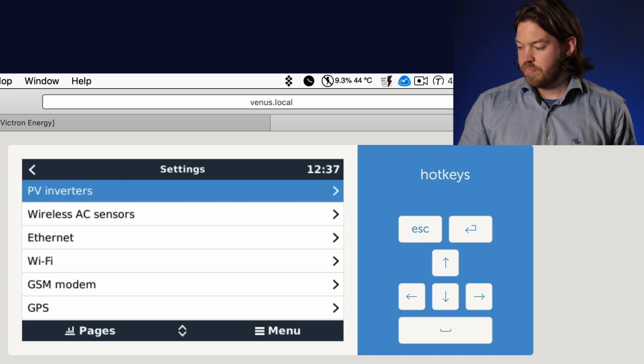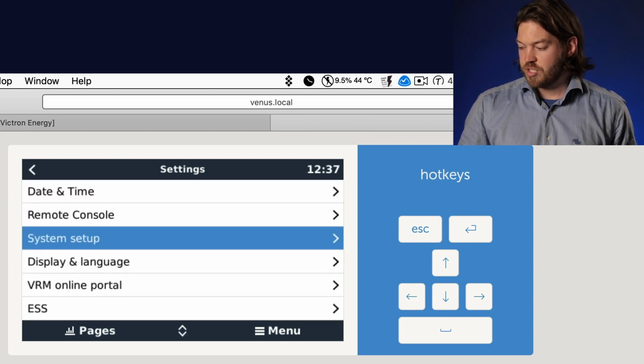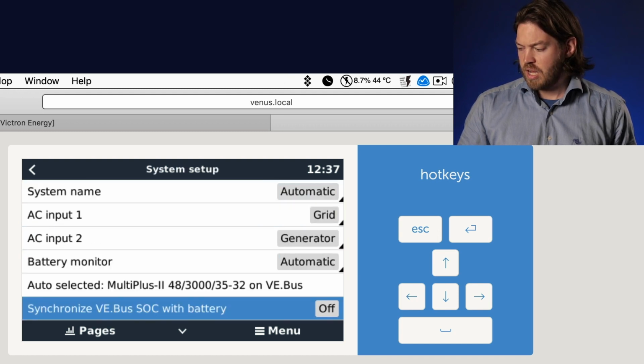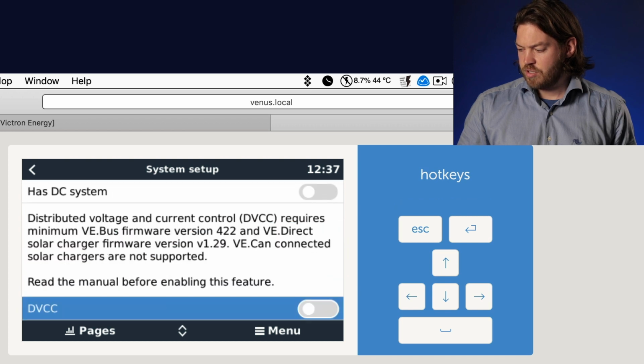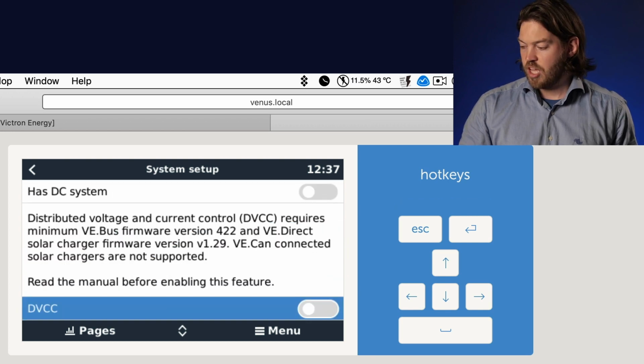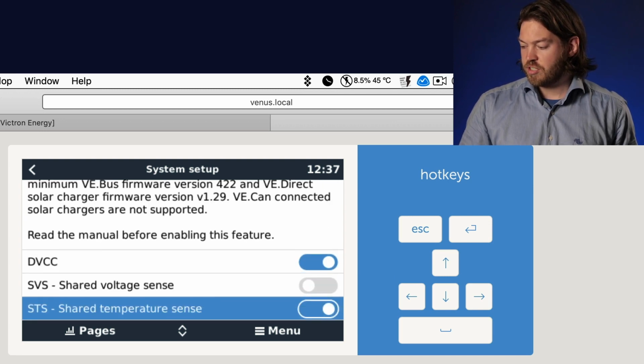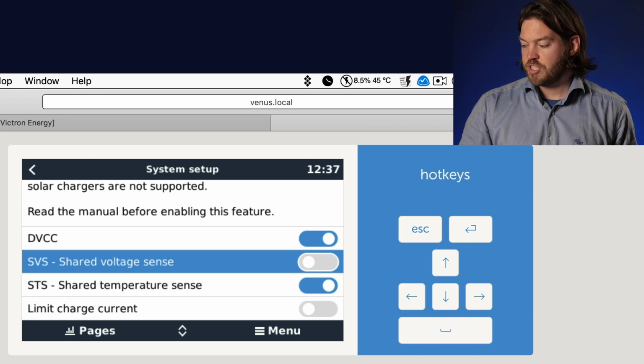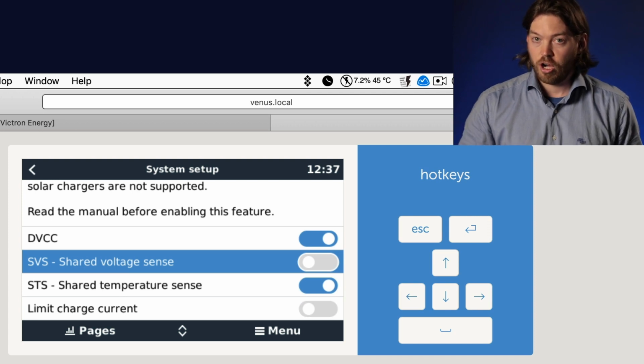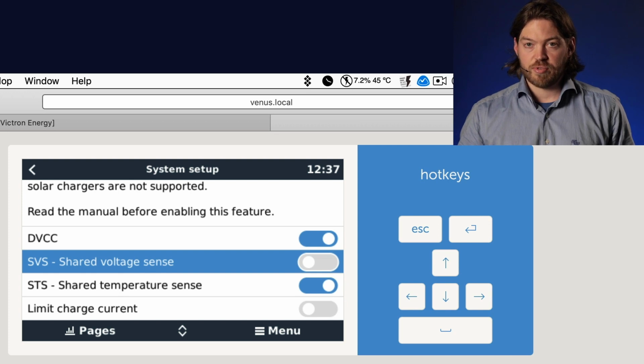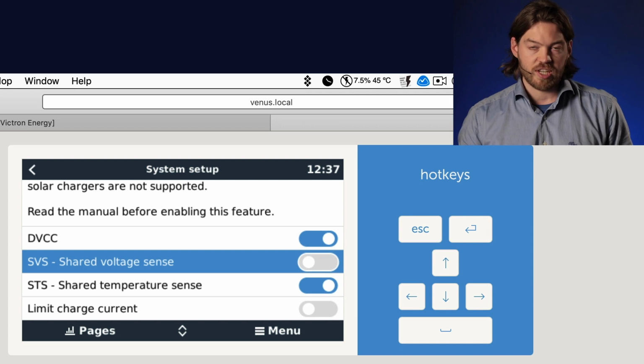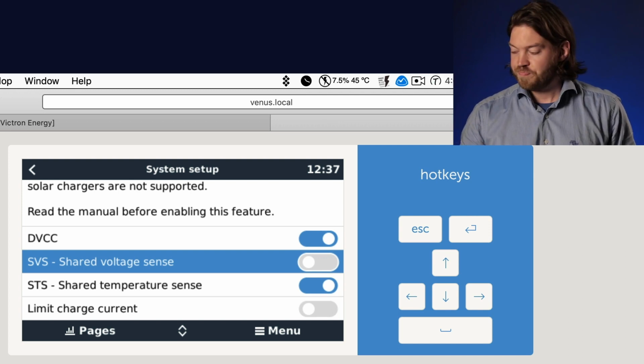I'm now going to go up to the system setup and then down to DVCC and turn this on. I'm also going to go to the next setting, which is the shared voltage sense, and I'm going to make sure this is switched off. This is actually a more stable system with this switched off, because most of the MultiPlus units and the MPPTs have a good voltage sense on their own, and it tends to give a more reliable charge.